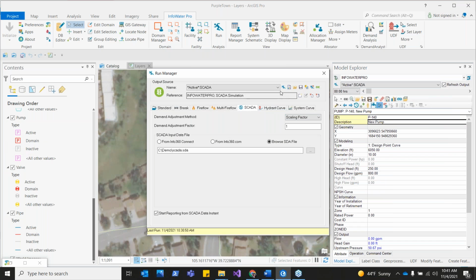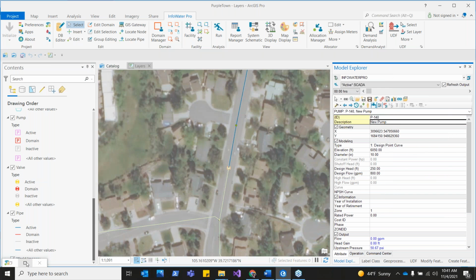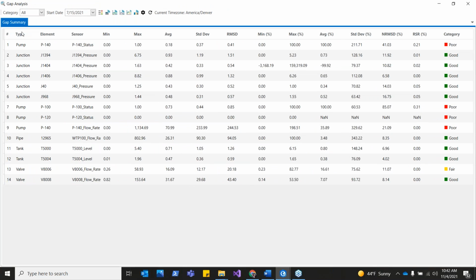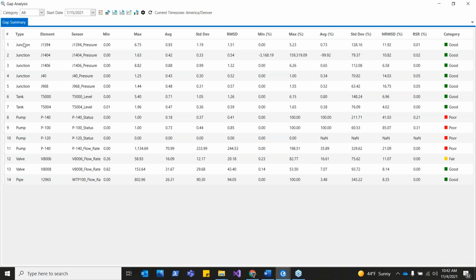As she does that, this is of course a little bit scripted, but if we had looked at those graphs, you'd see that the tank in the model is going down to 78, but in the measured data, it's only getting down to 80, and then the pump is kicking on earlier in real life than in the model. So that's why that change from 78 to 80 could be a logical one. A little look behind the screen.